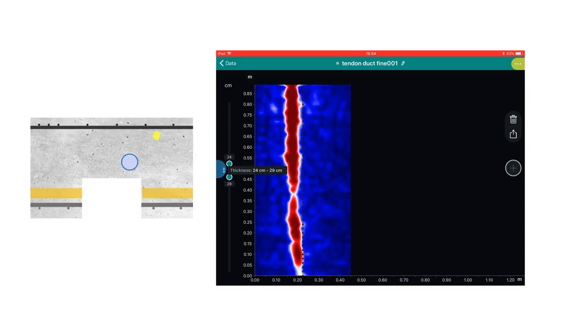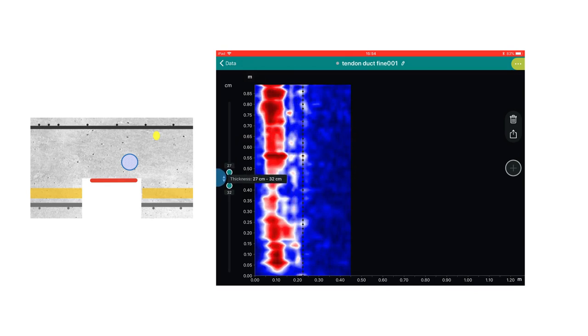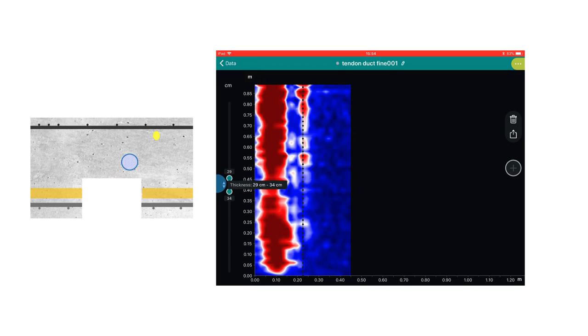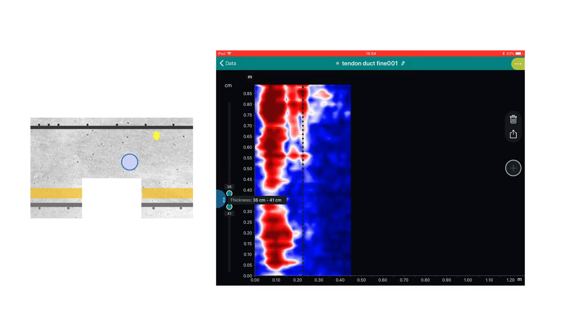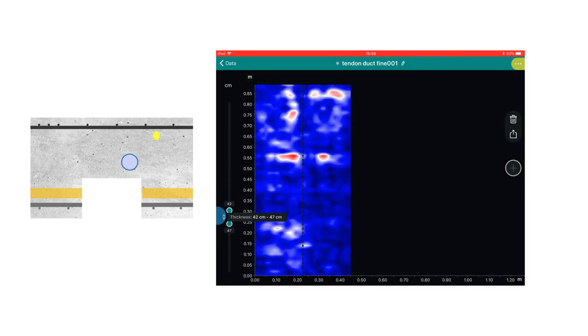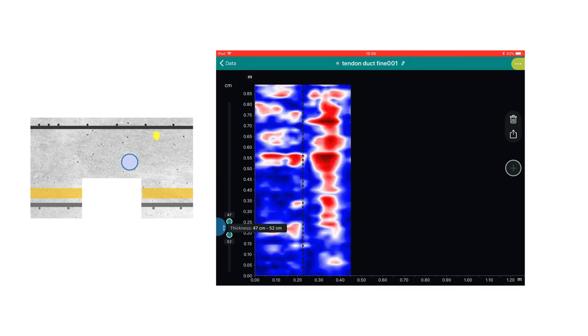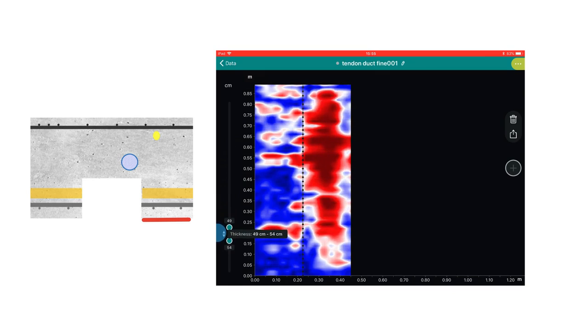The end view of the test block shows the relative depths of the various objects. We see the first back wall echo at a depth of 30cm, with a shadowing effect from the tendon duct. And as we move the slice deeper still, we see the next back wall echo at a depth of 50cm.